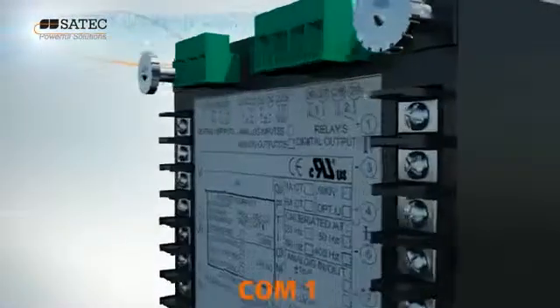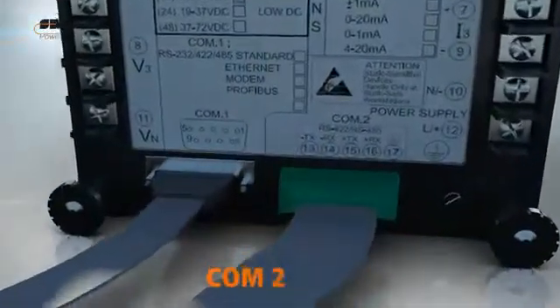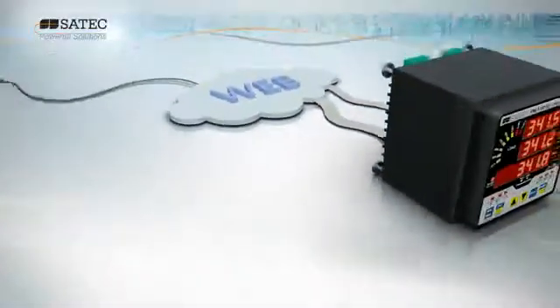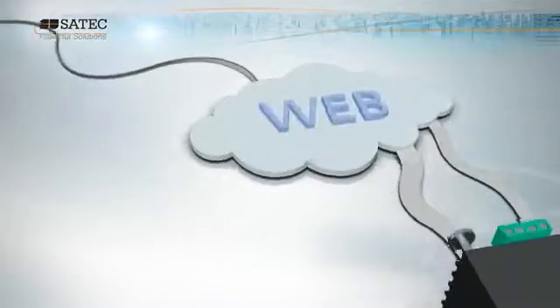The basic PM175 comes with two built-in communication ports, allowing both local and remote automatic reading and setup through supplemental communication or user data acquisition software using Modbus and DNP 3.0 protocols. The meter fully supports a wide range of communication platforms including Ethernet, wireless, and Profibus.